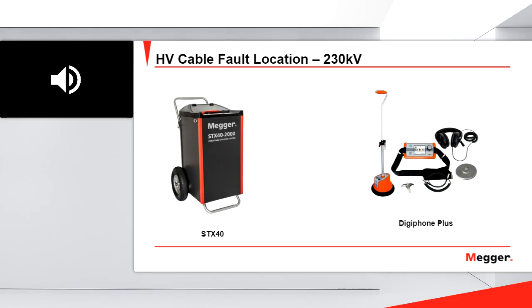As I said at the beginning of the presentation, it is focused on medium voltage cables, okay? But the operation principle is exactly the same for fault location on high voltage and transmission cables. The example that I would like to show is a fault location made on a 230 kV cable. In this case, we use the biggest portable thumper we have in Megger, the STX40, and we use our pinpointer, the Digiphone. So let me show you this example in the field.